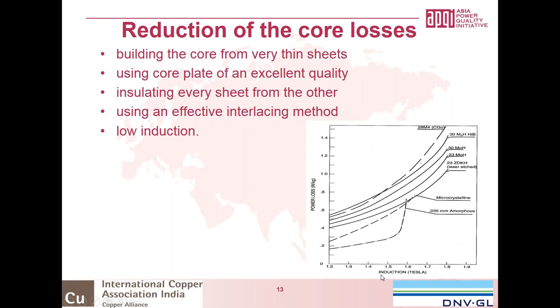In this picture you will see on the horizontal axis the induction in Tesla, and on the vertical axis you will see the losses within a core. And there you will see that we have different types of materials, M4, CGO, and laser scratch, and you will see that the laser scratch material compared to the CGO has a lower loss at almost every rating of the Tesla. You will also see the number mentioned over there, and that's the thickness of the sheet.